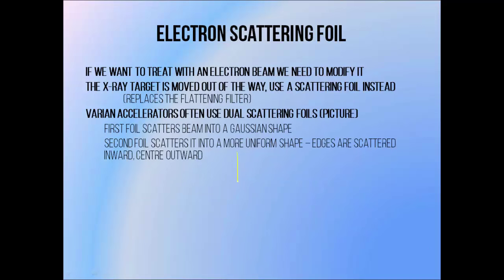If we want to use a linac to produce a clinical electron beam, we move the x-ray target out of the way. The electrons at this point are still in the form of a pencil beam, which is not very clinically useful — it's much thinner than most of the targets we want to treat. So we convert it into a more broad and clinically useful shape using scattering foils further down in the treatment head. Varian accelerators use something called a dual scattering foil, which consists of two thin pieces of metal that spread out the beam by scattering. The beam hits one layer and is spread out a bit, then hits a second layer which further adjusts its shape.